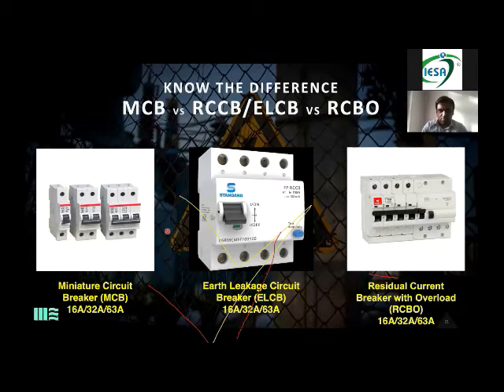At the start of the season, when the material is going out of our warehouse, we do a load test. We give the MCB 10 kilowatts, what it is meant to take, like a 32 amp MCB can take a 10 kilowatts load. We see whether it trips or not. If it doesn't trip, obviously it is faulty. And if it trips, then obviously it is right. So those load banks can also be created on site.